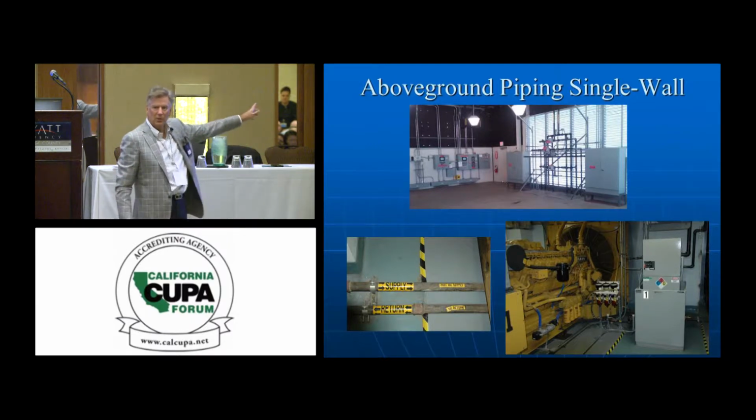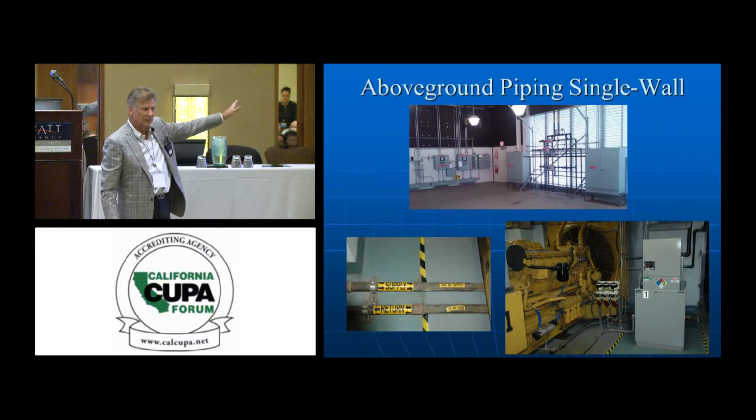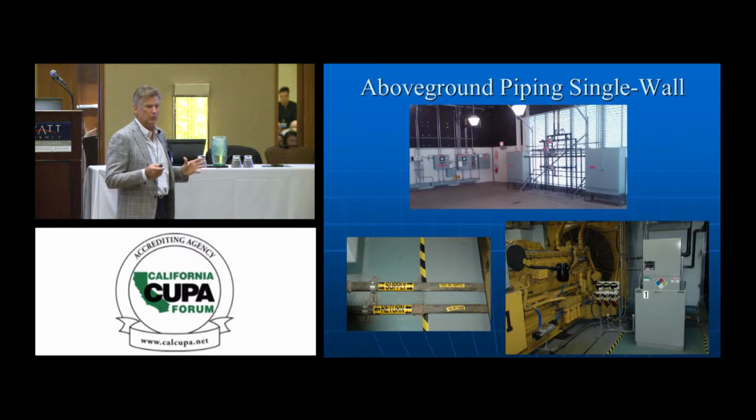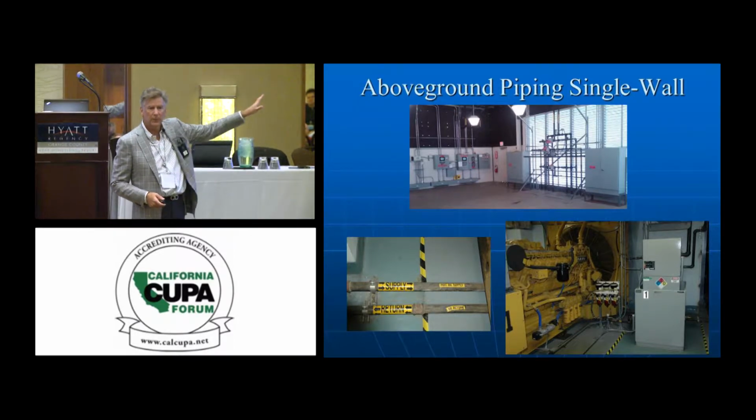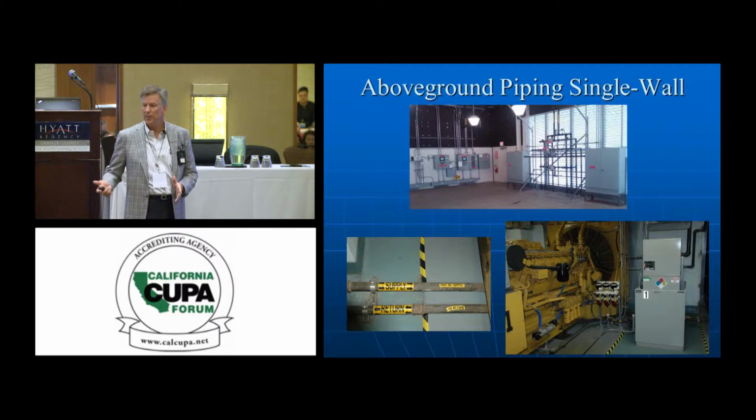But if I've got twin turbines in here coming in at 25 GPM, right? That's an enormous difference. Because when I go to restrict the flow as it's coming into the day tank, let's say down to 10 GPM, that's not going to matter because this is upstream of that. So in working with fire, normally what we just have here is an emergency shutoff and a daily inspection, and that tends to be the common solution to this. Does that answer your question?